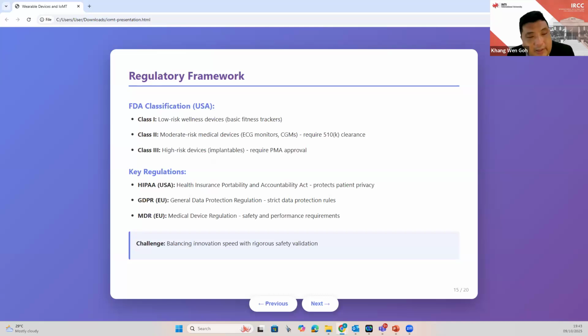Of course, the regulatory landscape for IoMT is very complex. So far, in the US only, the FDA classifies medical devices into 3 classes. Class 1 is very low risk, wellness devices. This is basically just a basic fitness tracker: how many steps, heartbeat, that kind of thing. Class 2 is moderate-risk medical devices like the ECG monitor, which requires 510(k) clearance. Class 3 is high-risk devices. Normally this one is implanted in your body.